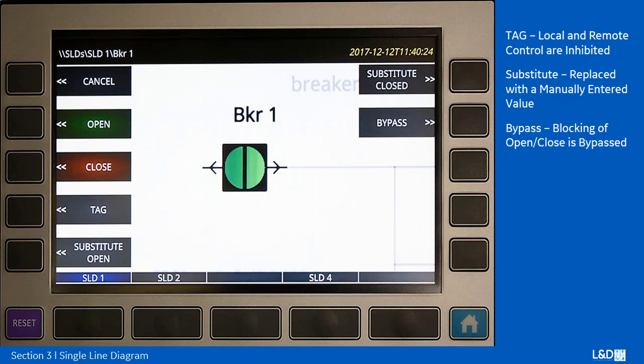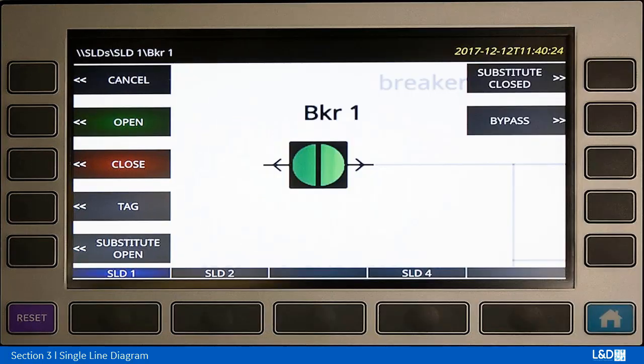The tag, if you select it, gives you an opportunity to inhibit the operation — both local and remote control of the breaker. The substitute replaces it with the manually operated value, and the bypass, once enabled, bypasses the blocking of the open or closing of that particular breaker.